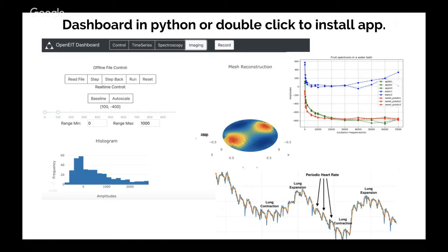So this is what the software looks like. You connect to the device, and you have 3 different choices of types of things you can do with it. You can get time series impedance data, which is down on the bottom right. So that's at 50 kilohertz, and I've attached it to my chest, and I'm measuring both my lung expansion and contraction, and the blood moving through my heart valves. What's cool about that is that it's not an ECG. It's a different kind of measurement. It's measuring the material change due to the dielectric materials, the impedance changing. So it's a mechanical change. So your heart has blood, the valves open and shut, and you're measuring that blood flow change. You want to see how much air you've taken into your lungs. It's measuring that change, which is quite different from just the sort of passive electrical signal.